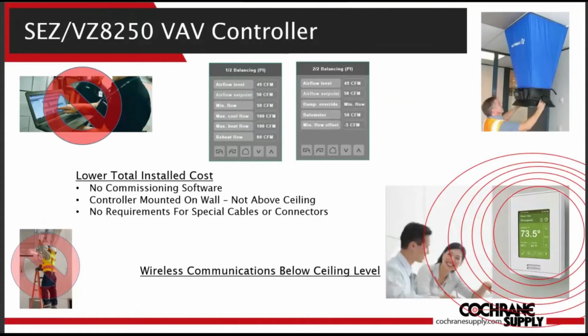What about the balancer software to run on a computer? There's no balancing software. Settings and configuration are performed through the touchscreen. There's no need to bring out a ladder, remove ceiling tiles, or worry about special devices or cables to connect to the controller. Moreover, if your installation is suited to wireless communications, the controller is located on the wall, not above the ceiling level, so there's a significantly reduced chance of the wireless communication signal being interfered with by I-beams, ductwork, or equipment installed above the ceiling.